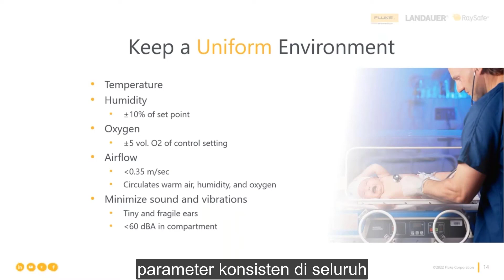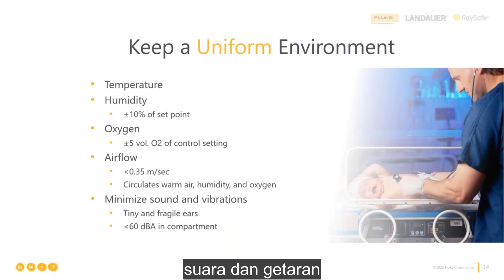Temperature should be the same in all parts of the cabinet. Humidity and oxygen should be at appropriate levels and stay constant. The airflow above the mattress should not exceed 0.35 meters per second, and it should stay relatively constant to help circulate temperature, humidity, and oxygen, and ensure that all parameters are consistent throughout the cabinet. The incubator also helps minimize sound and vibrations. Below 60 decibel adjusted is acceptable for this infant's tiny and fragile ears.